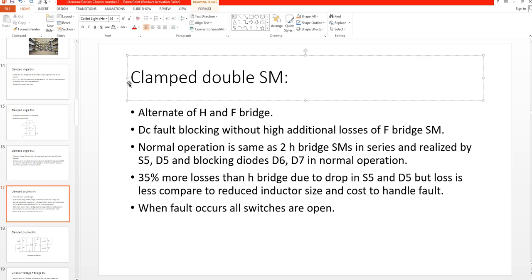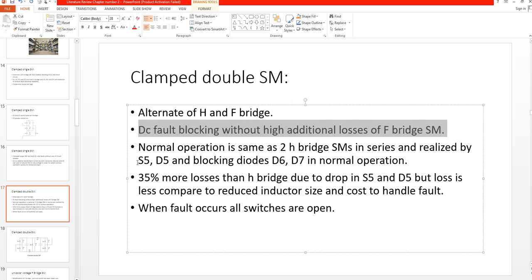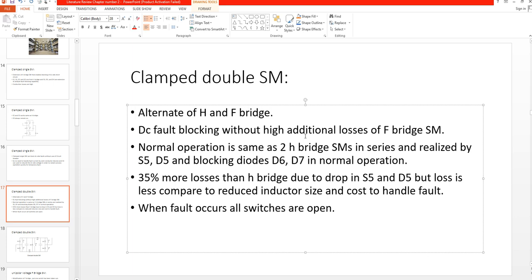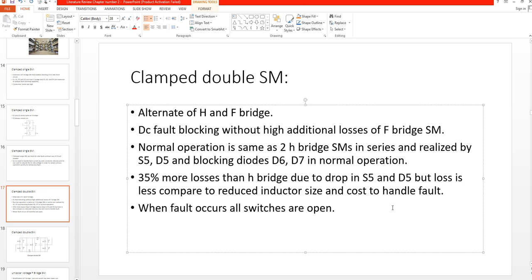Now we discuss the clamped double submodule topology and how it differs from the clamped single submodule. It is an alternative combining half bridge and full bridge, providing DC fault blocking without the additional losses of a full bridge. Normal operation is the same as two half bridge submodules in series, realized by S5, D5, and blocking diodes D6 and D7. It has 35% more losses than half bridge due to voltage drop in S5 and D5.